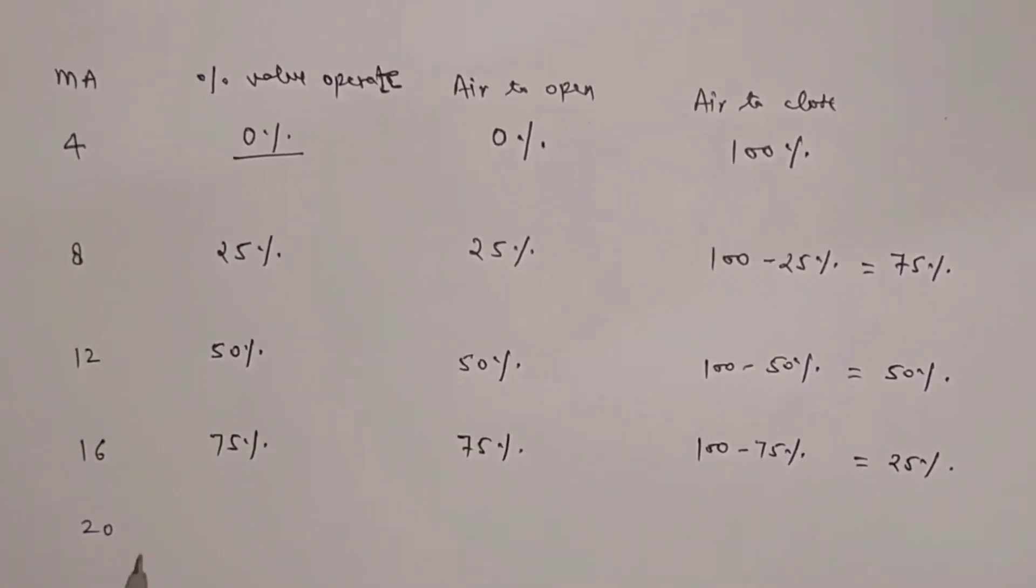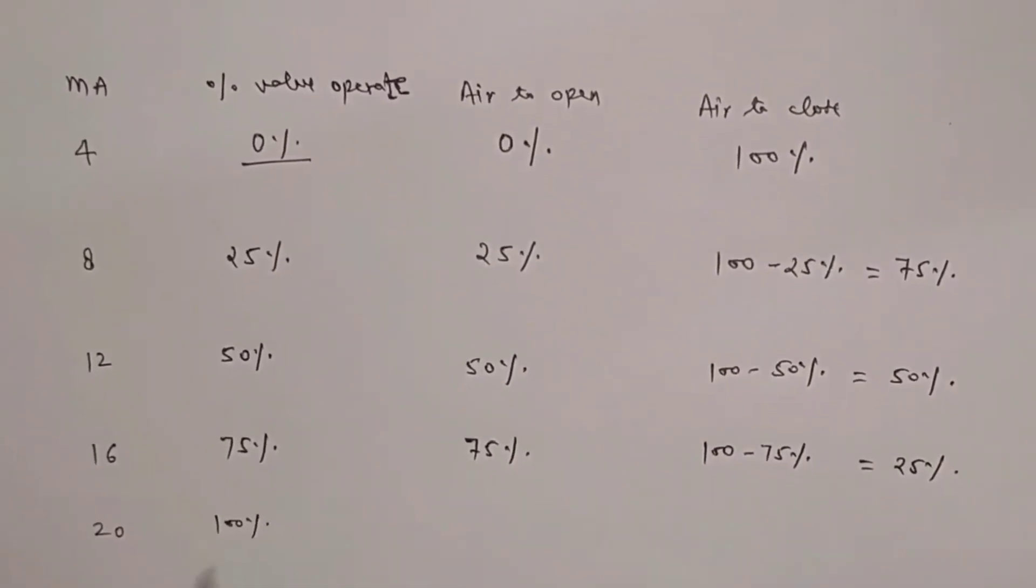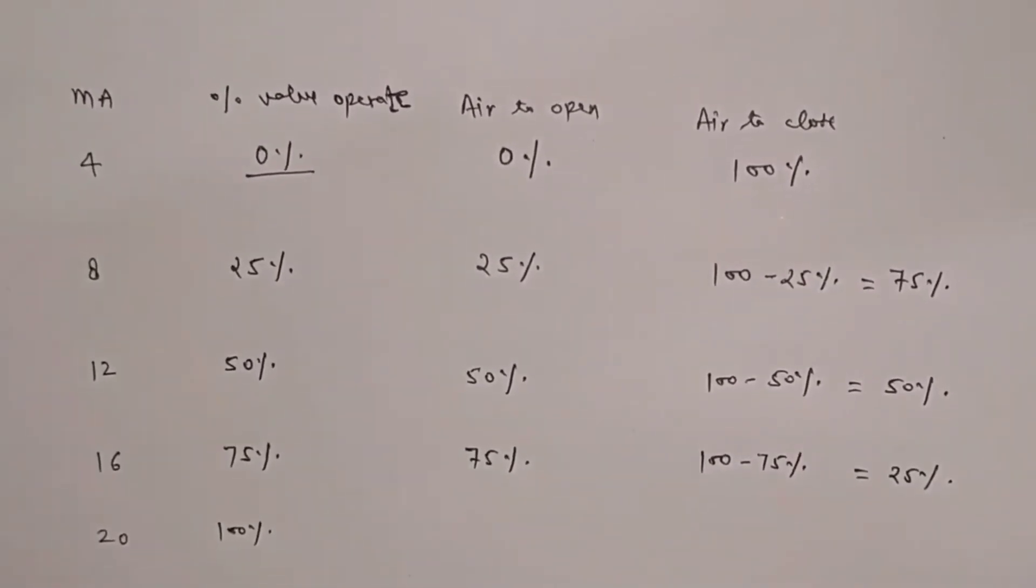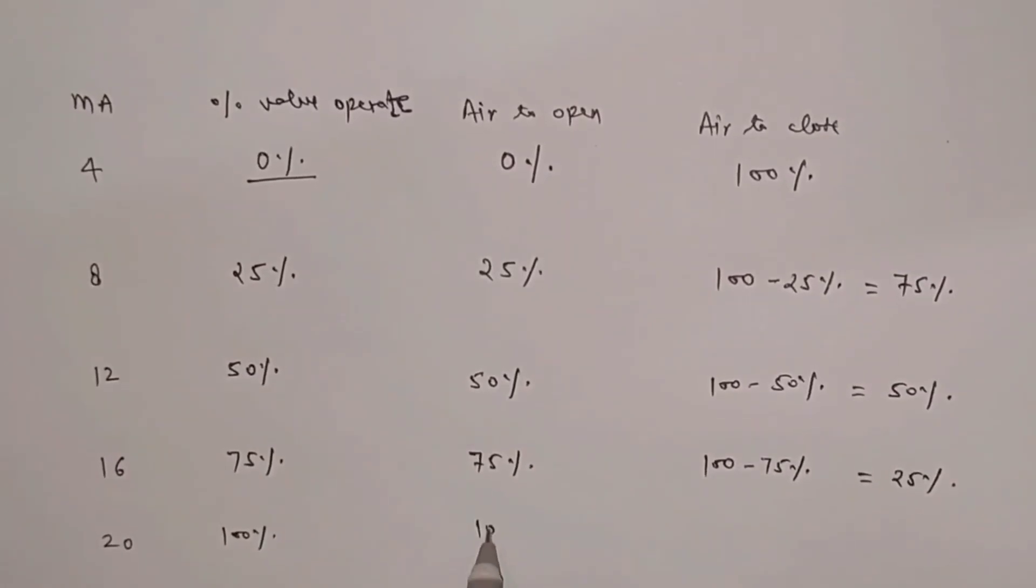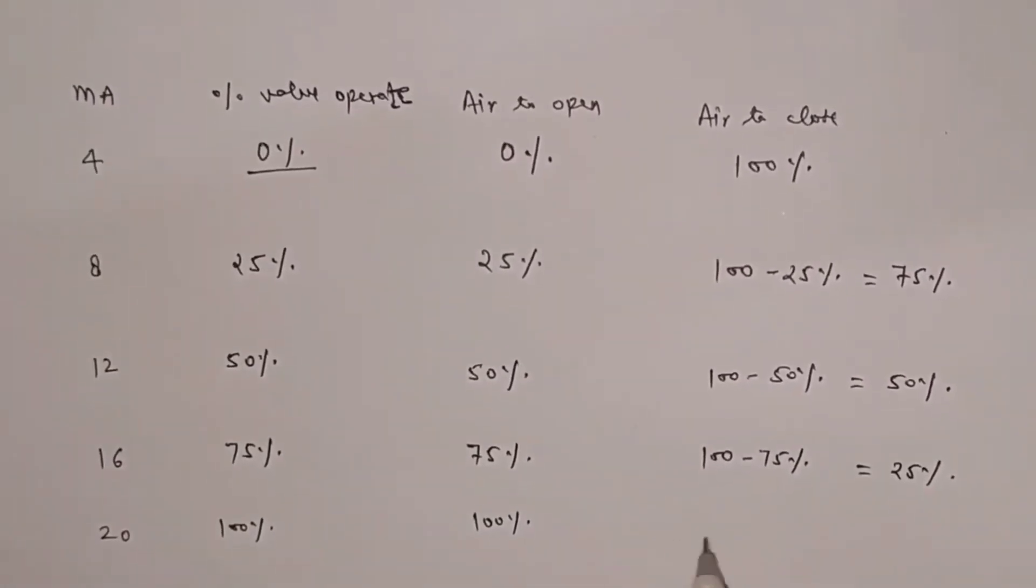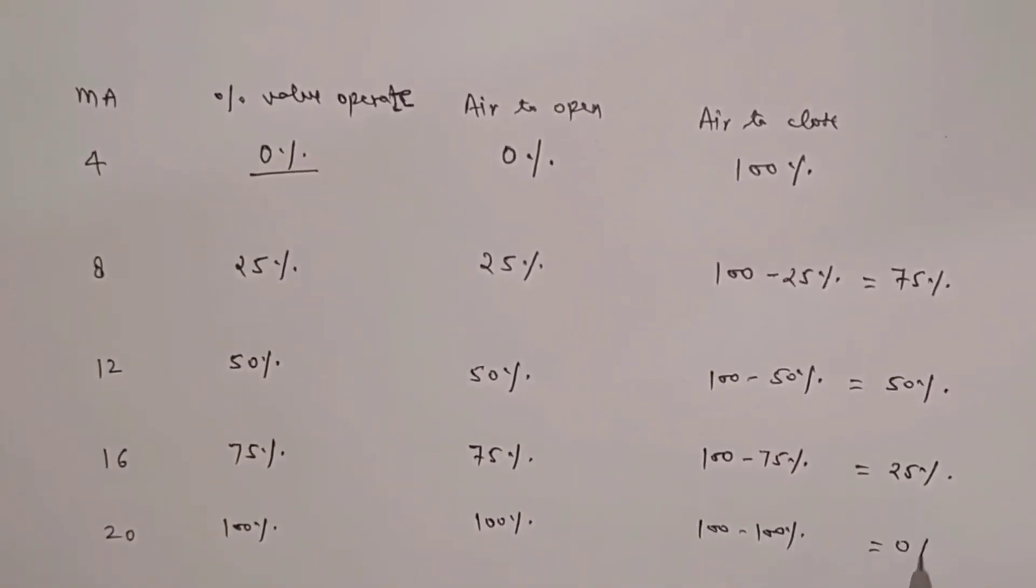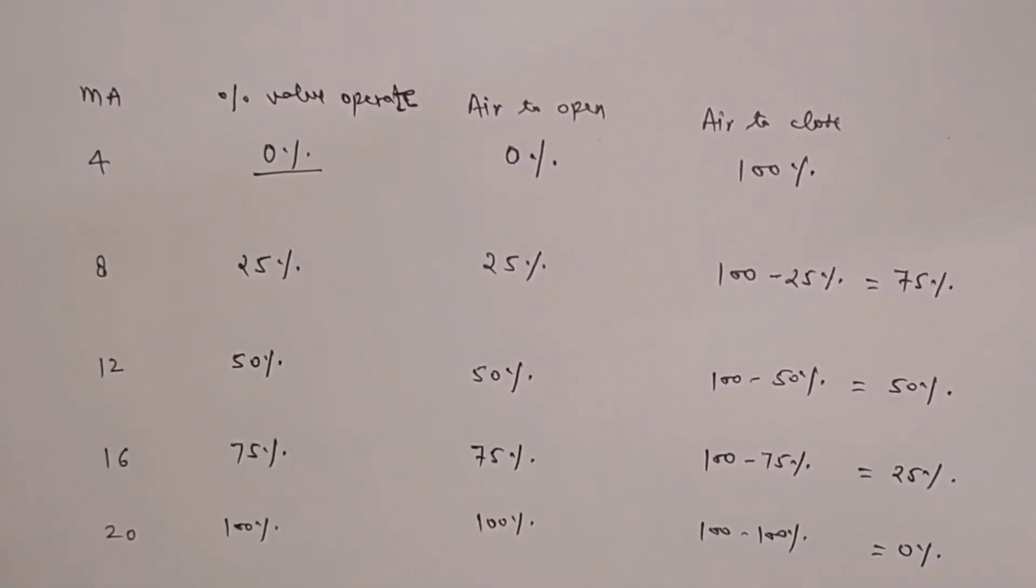Similarly, at 20 milliamp signal, it will be 100%. Now the opening percentage of air to open control valve is 100%. And air to close control valve opening will be 100 minus 100%, means 0%.